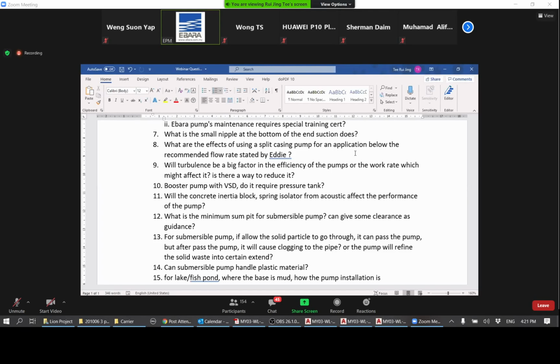What are the effects of using a split casing pump for an application below the recommended flow rate? Usually we are highlighting this because we want to improve the situation. We want you to improve that as well, what we call BEP, which is the best efficiency point. If you look at the pump curve, it will state the maximum efficiency and the range of good efficiency of that pump.